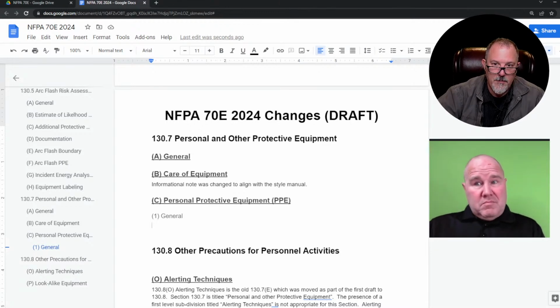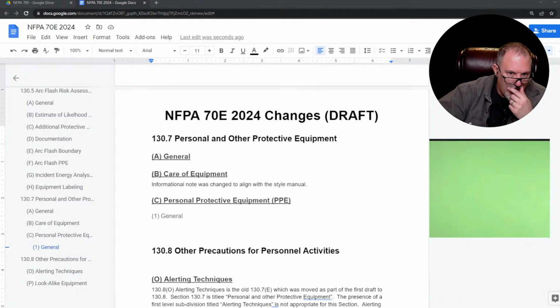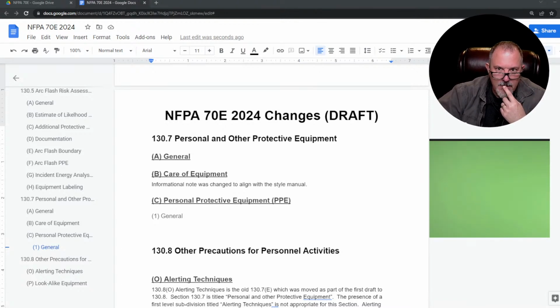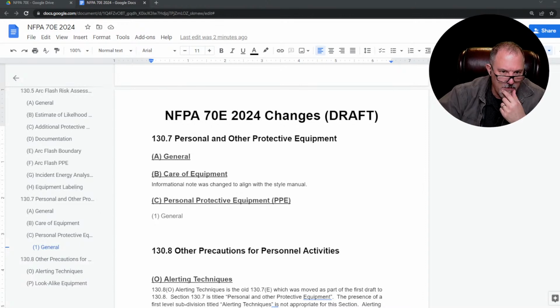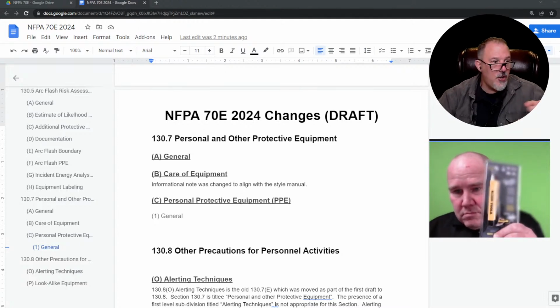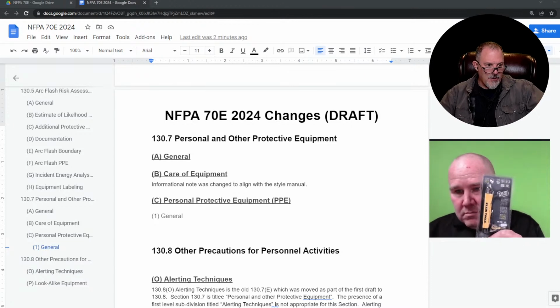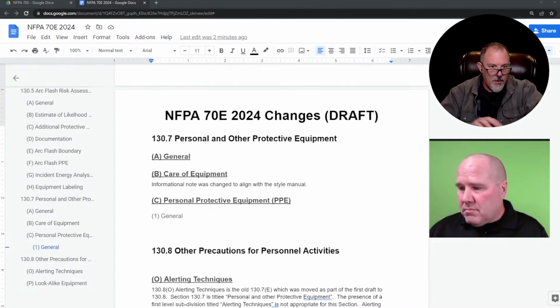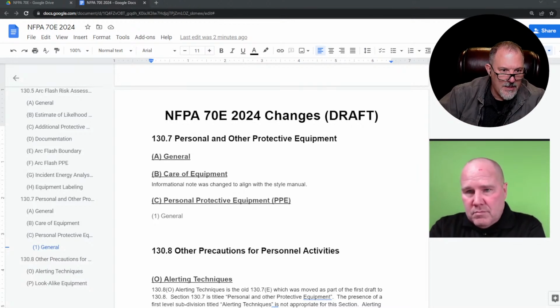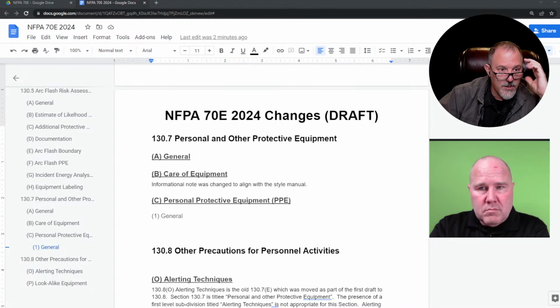And what this has to do with, and I remember this discussion at the committee, is the previous example of a risk reduction method in item 1 in this note. You're talking about these things. No, you know what? That's similar, I agree. That's a capacitive thing. What this one was talking about is, it does say use of non-contact capacitive test instruments or a permanently installed metering device.